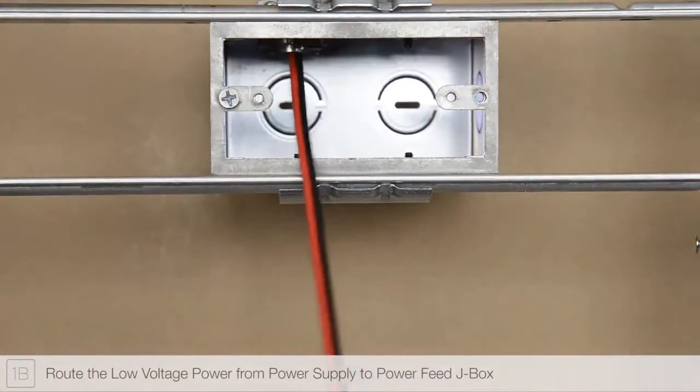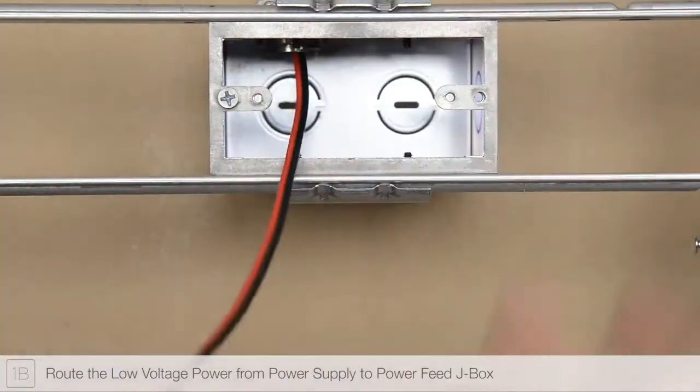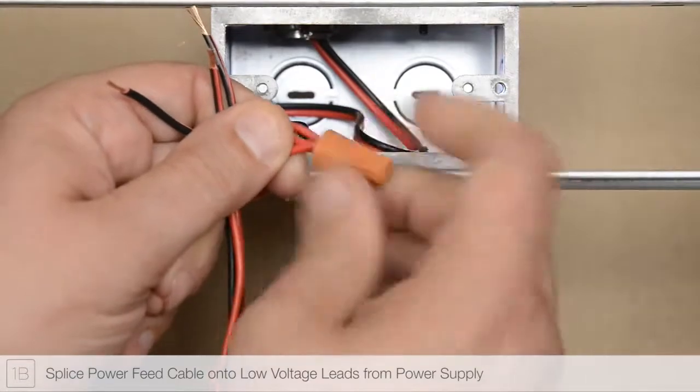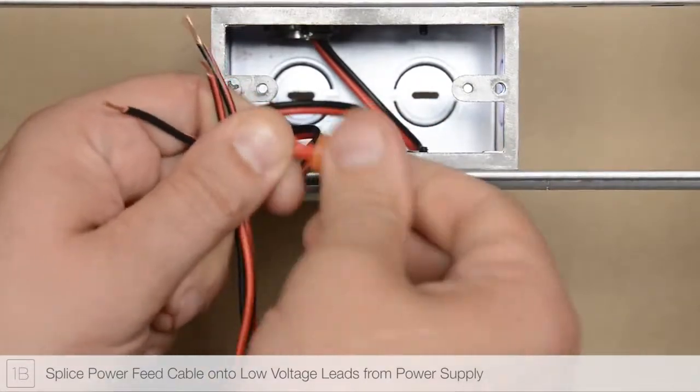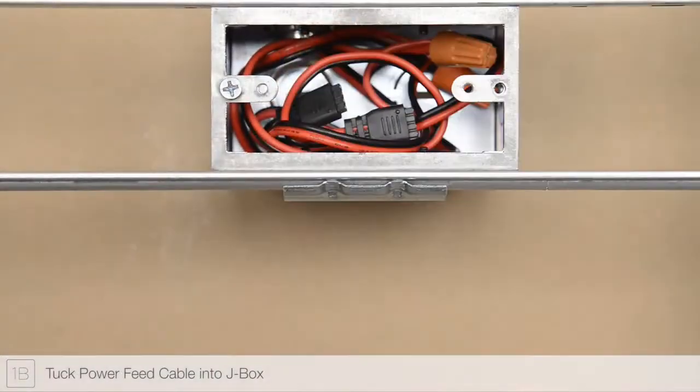Route the low voltage power wires from the remote power supply to the power feed junction box. Splice the included power feed cable to the low voltage power wires using wire nuts. Place all electrical connections into the junction box.